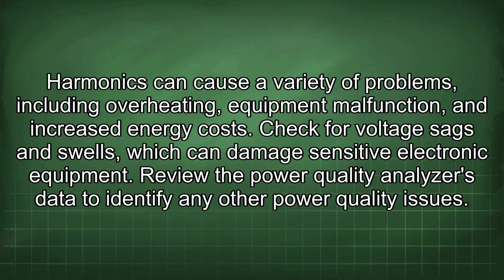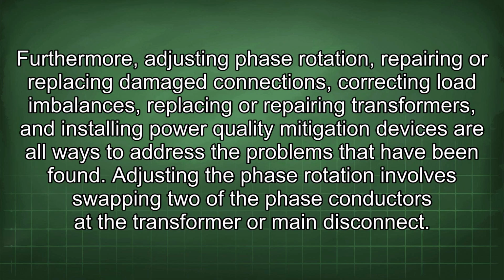Check for voltage sags and swells, which can damage sensitive electronic equipment. Review the power quality analysis data to identify any other power quality issues. Furthermore, adjusting phase rotation, repairing or replacing damaged connections, correcting load imbalances, replacing or repairing transformers, and installing power quality mitigation devices are all ways to address the problems that have been found.